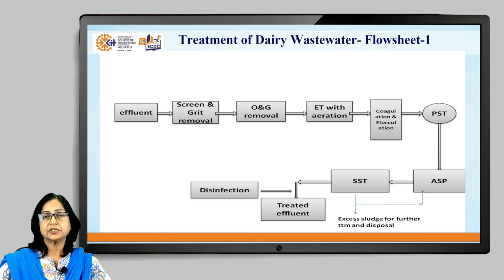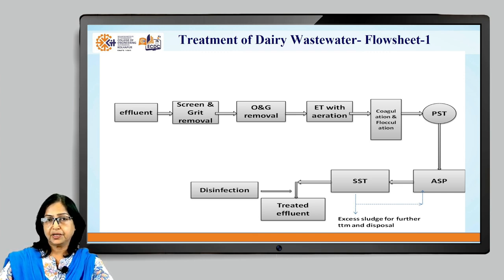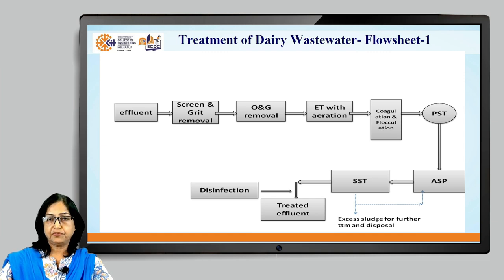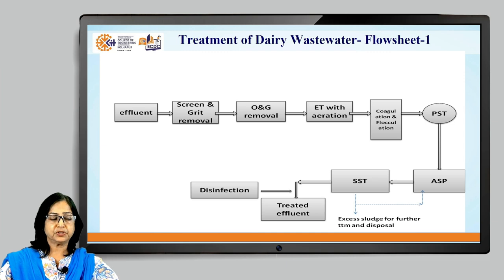In flow sheet 1, the effluent is taken to screen and grit removal, followed by oil and grease removal, then equalization with aeration, and coagulation-flocculation-settling. The supernatant from the primary settling tank (PST) is taken for secondary treatment — the activated sludge process followed by a secondary settling tank — while sludge is sent to a sludge drying bed. Excess sludge is sent for further treatment and disposal; part of the sludge is recycled to maintain MLVSS. The supernatant from the secondary settling tank is disinfected and then disposed of as treated effluent.